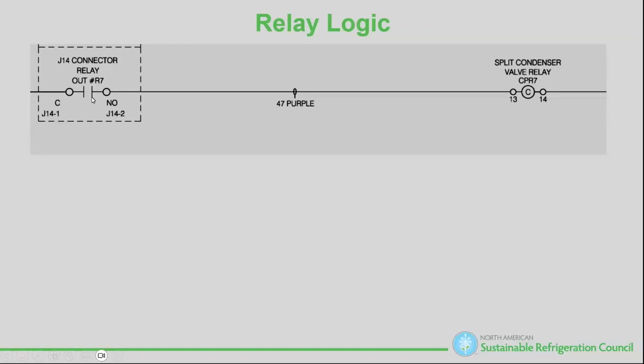These only have Form A contacts. Form A versus Form C. Form C has a common, a normally open, and a normally closed. Form A simply has a common and a normally open. You can't make that decision, you can't wire it normally open or normally closed. So sometimes you have to use your relays to finish out the logic.